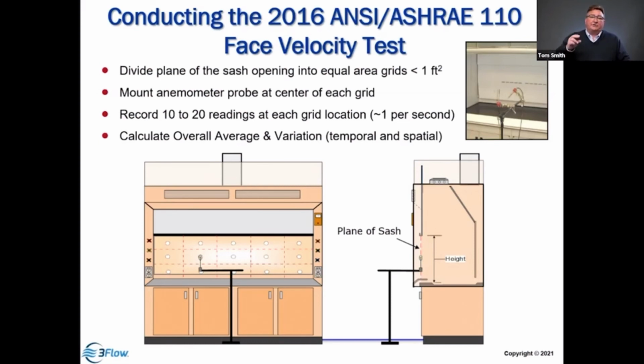So we want to use this technique of mounting the probe, moving it from point to point across the traverse, so that we increase the accuracy and precision of our measurements, and therefore have better data to use to confirm flow or to verify the operation of the hood. So again, go back to this: our integrity is directly linked to accuracy and precision. We want to collect data that's as accurate and repeatable as possible, so that it can be done by any technician. You go in, you place the probe in these locations, you collect data, it gives you a value, you compare period to period, and you know that you have consistency from which to judge the operation of the hood.